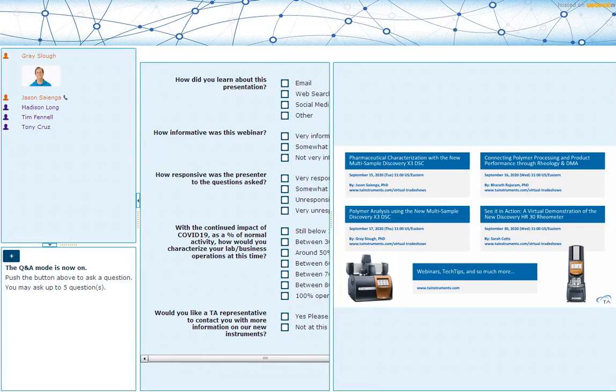In some of our other DSCs, we had an opportunity to kind of switch through the different heat flows. So if you had a 2500, you could run in a T1 mode or the T4P mode. Because of the way this cell is designed, there really is only a specific heat flow for this system. So there's no changing, there's no selecting. You're going to get all the advantages of the T0 heat flow, but also because there are 3 samples in this cell, 4 pans rather, at the same time, you do have to enter in the pan masses for each of those.